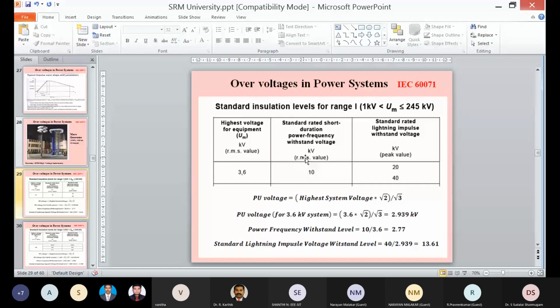Now, the power frequency withstand voltage they have given us is 10 kV. So 10 divided by 3.6, and both are in RMS. Please see, both are in RMS because both are in the power frequency range. The power frequency withstand level, 10 divided by 3.6, is nothing but 2.77.